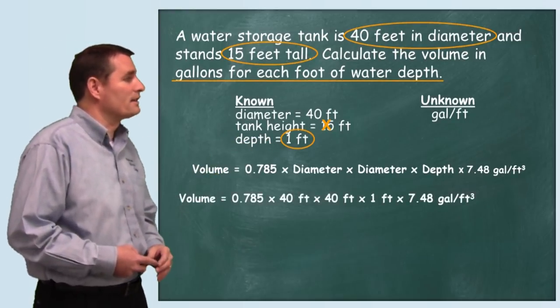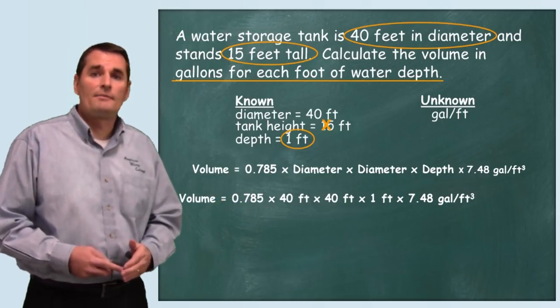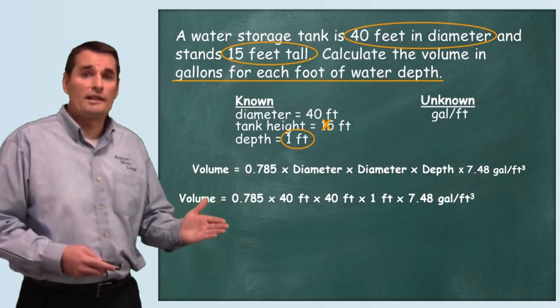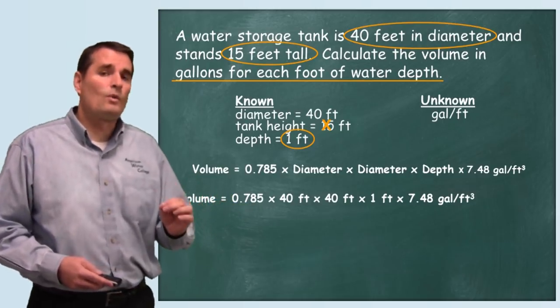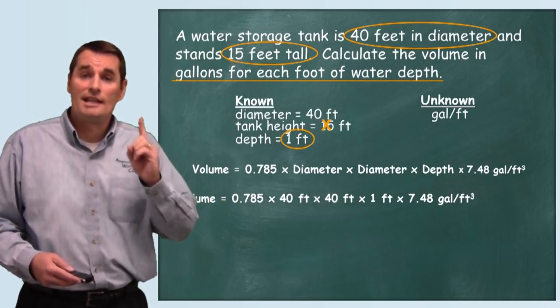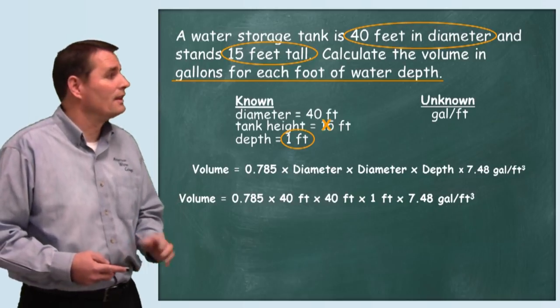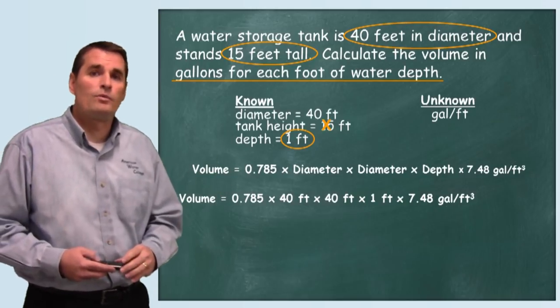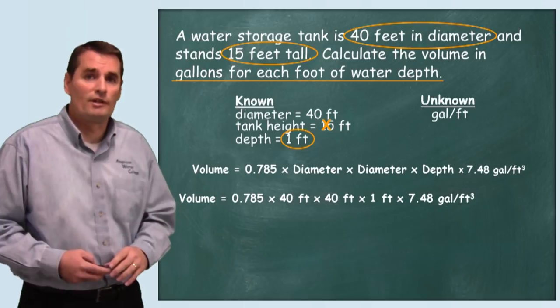Now when we plug our numbers in: 0.785 times the diameter twice which is 40 times the depth which is one foot. Remember we don't use the 15 feet because we're only looking for how many gallons in one foot of tank depth, times our unit conversion of 7.48 gallons per cubic foot.